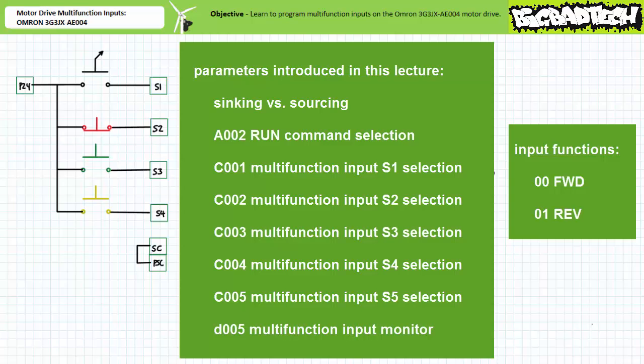In conclusion, we installed external remote input devices and learned to program the OMRON 3G3JX AE004 motor drive to recognize and respond to these remote inputs. We changed the drive from sinking to sourcing input format, examined 00 forward and 01 reverse functions in detail, and discussed the proper sequence to hand off control to these remote inputs. Long story short: don't hand off control to the multifunction inputs until you first assign them the proper functions. Any shortcuts in this process could have disastrous consequences, given an input might have a pre-assigned default function incompatible with the present configuration and application. Finally, we learned to monitor the logical status of remote input devices using the multifunction input monitor function.